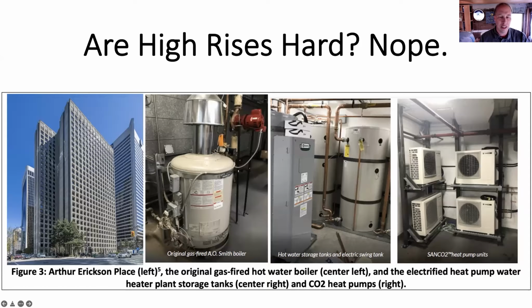Here's the old gas boiler, and here are the new hot water storage tanks and what's called a swing tank, because heat pumps usually need more storage since they don't have as much instantaneous capacity. Here are the heat pumps down there—they're all collecting heat from the air and stripping it, so it's chilling the air.